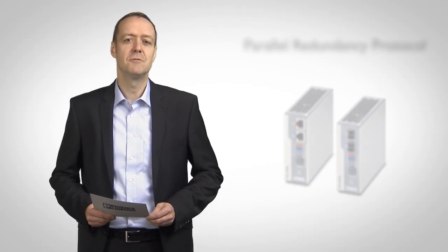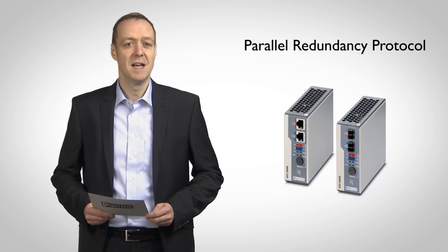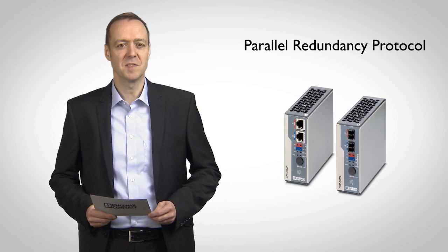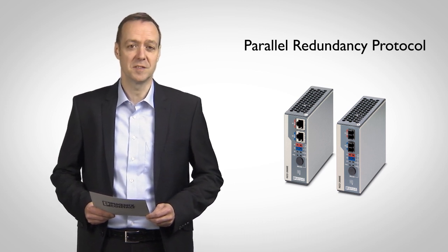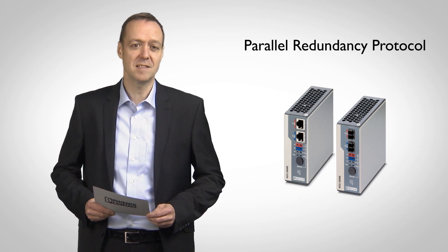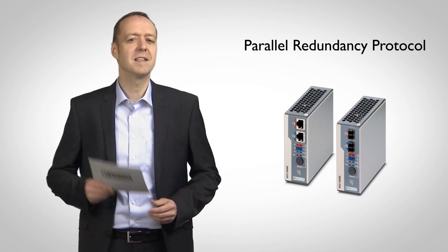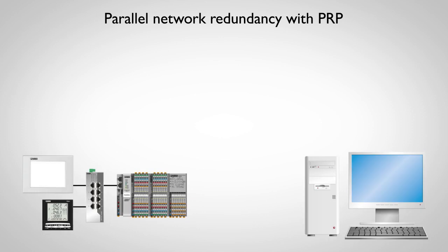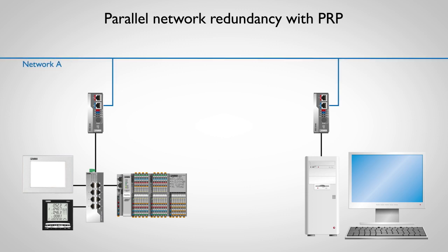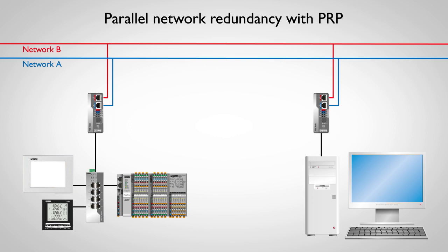With the Parallel Redundancy Protocol, also known as PRP, Phoenix Contact offers a redundancy mechanism which ensures interruption-free Ethernet data transmission even if parts of the network fail. Now let's take a closer look at it. Each device is integrated into the network via a PRP module. The modules are connected with one another via two separate networks, and data packages are therefore transmitted in parallel via both networks.